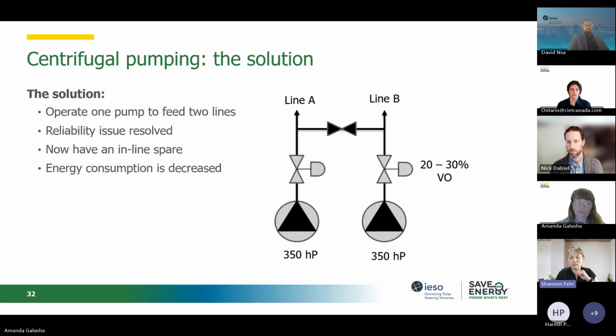We made this change and tried it out, and found out the pumps ran better. The reliability issue was resolved. Now the mill has an inline spare. You can do maintenance on the fly, and energy consumption was decreased. So this is how you can couple solving the problem with the energy efficiency opportunity.